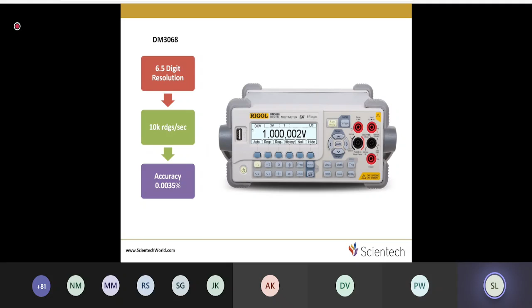So at the quality level, where I am doing sample testing, taking one sample from say 100 sensors produced, I can use the low speed, high resolution multimeter. During the production process, I can use the high speed multimeter, because of the productivity I need in a day. So that is a 6.5 digit resolution, 10K readings per second, and accuracy of 0.0035%.